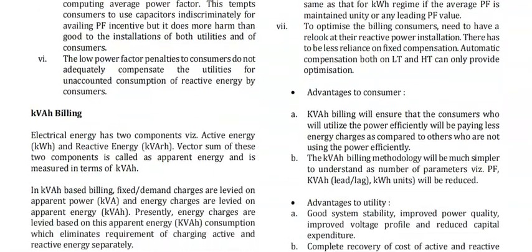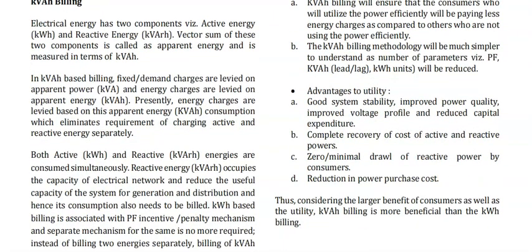Then we will read about kVAh billing. What is kVAh billing? Electrical energy has two components, active energy and reactive energy. Active energy is kilowatt hour billing and reactive energy is kVARh. The vector sum of these two is called apparent energy and it is measured in kVAh. Vector sum of real and reactive. In kVAh, that means apparent billing, the base billing, fixed demand charges are levied on apparent power kVA and energy charges are levied on apparent energy kVAh. Presently, energy charges are levied based on apparent energy. Now we are using kVAh billing, which eliminates the requirement of charging active and reactive energy separately.